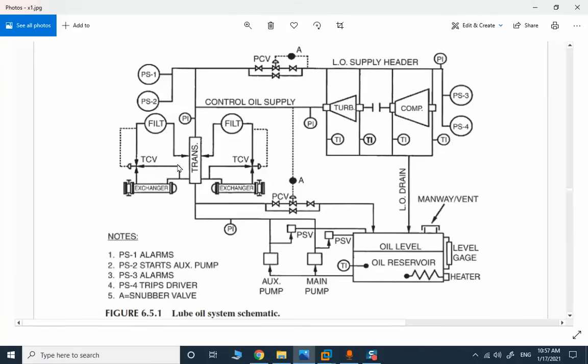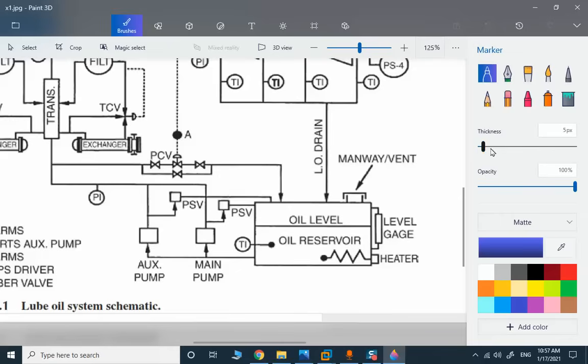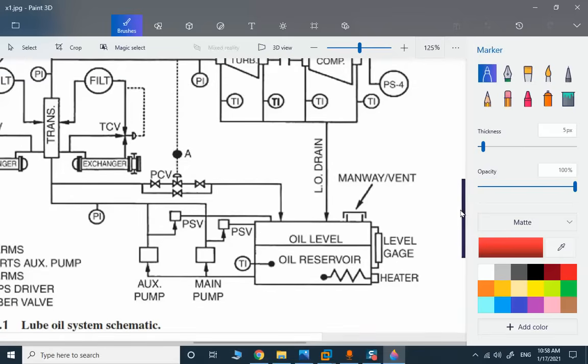This is the simple structure of the oil circuit in a gas turbine or compressor that I will explain in detail. The first part related to the oil circuit is the oil tank or oil reservoir. We need to monitor the level of the oil and the temperature at the same time. If the level is in critical mode we need to shut down or issue alert signals, and if temperature is within some low limit due to ambient temperature, we have this heater here to warm up the oil for better operation.